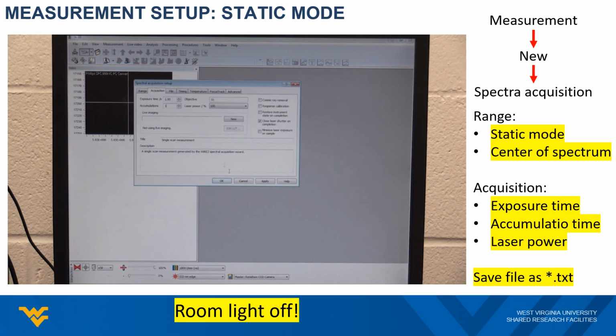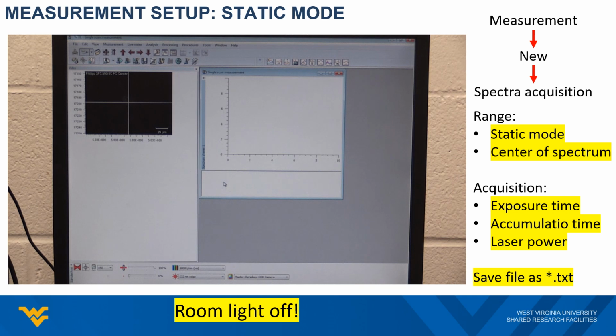Under the Acquisition tab, similarly, you could determine the measurement parameters, including the laser power to be used, exposure time, and number of accumulations. After that, press the OK button. This will bring you a blank window which carries all the measurement parameters. Then locate the Run button, click it. It will open the laser shutter and start the measurement. Once the measurement is done, the shutter will be closed, and then you could save the file into TXT format.